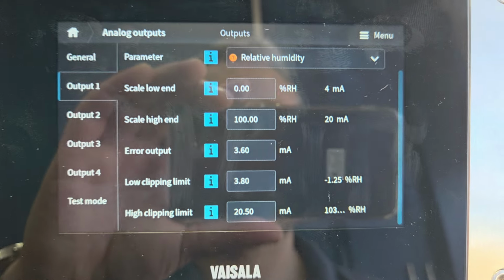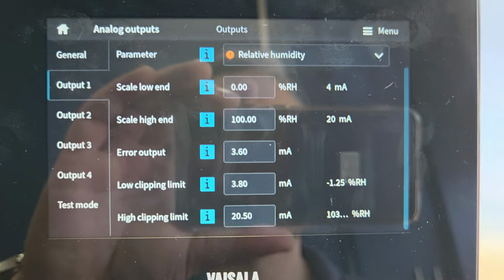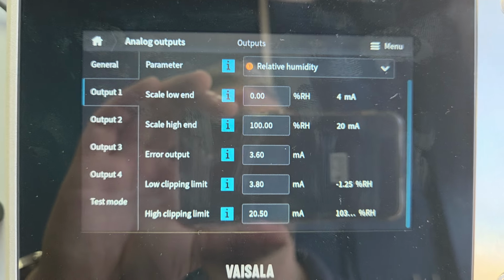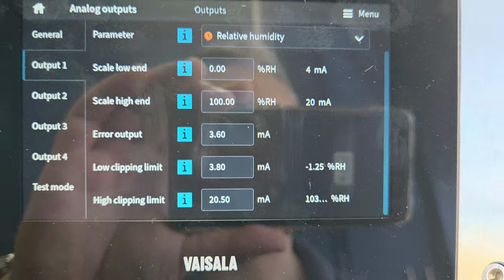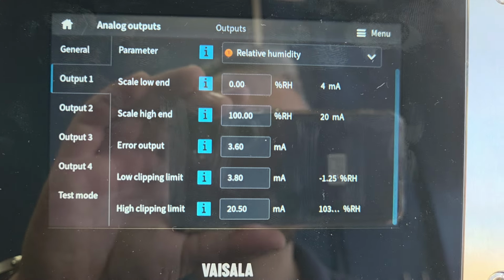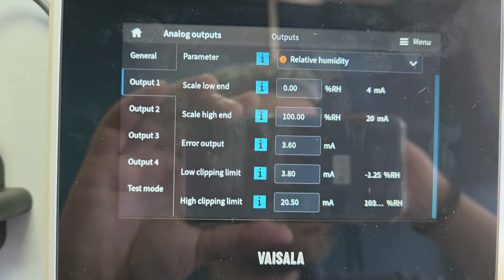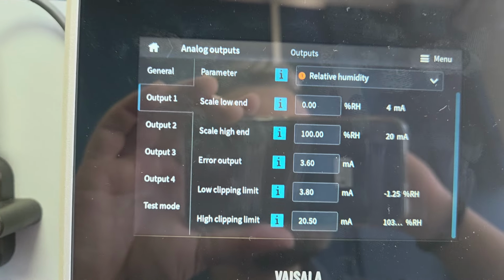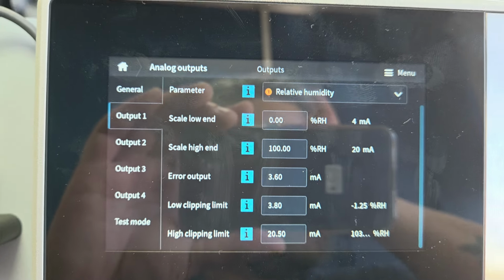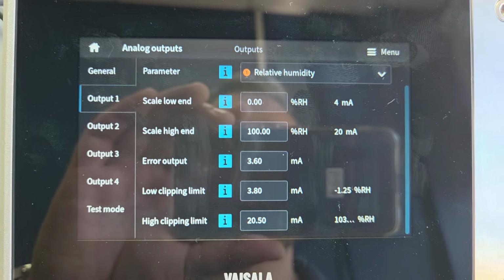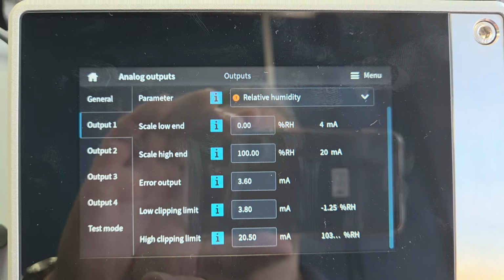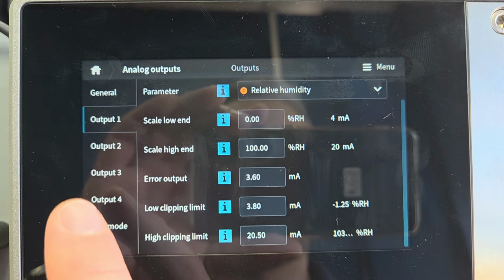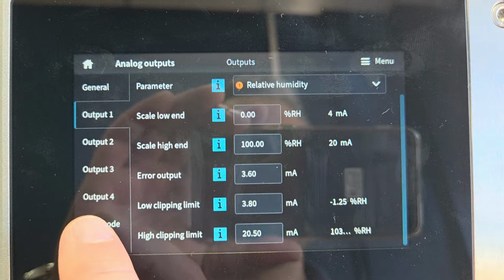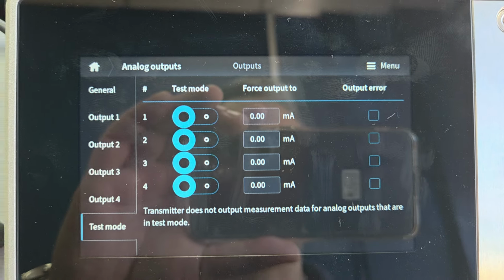But if it was temperature, for example, then you would scale it 0 to 100 degrees, but you could obviously measure down to whatever 3.8 milliamps works out to, minus 5 degrees or something like that. And I think that 3.8 to 20.5 is NAMUR NE43 compliant. Don't quote me on that. Doing that from memory. 4 analog outputs, all set up the same, and a very useful test mode.